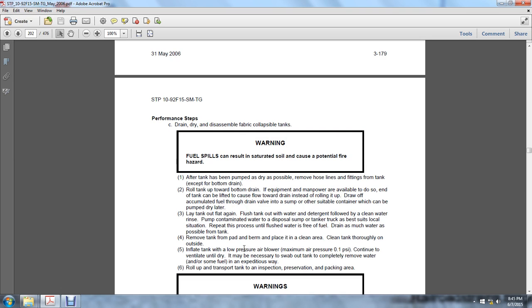Three. Lay the tank out flat again. Flush the tank with detergent and water, followed by a clean water rinse. Pump the contaminated water into the disposal sump or tanker, as best suits the local situation. Repeat the process until the rinse water is fuel free, and drain as much water as possible from the tank. Remove the tank from the pad or area and place it in a clean area. Clean the tank thoroughly on the outside.